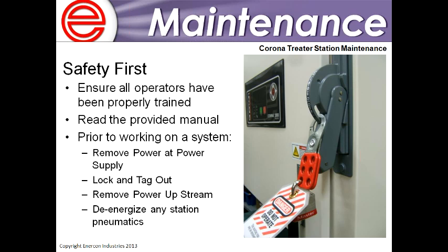Also, prior to working on the system, make sure that you follow your lockout, tagout procedures at your facility to remove and isolate all incoming power going to the system at the power supply. And this picture shows a typical place to lock out and tag out that power at the power supply, to make sure everything is completely safe at the corona treater before you're doing any adjustments or maintenance or cleaning.